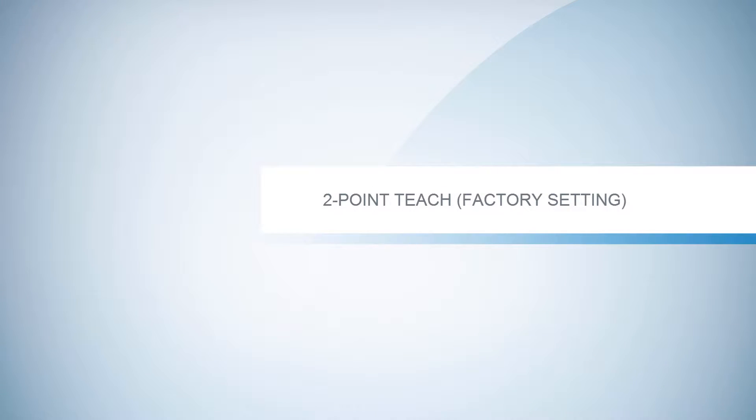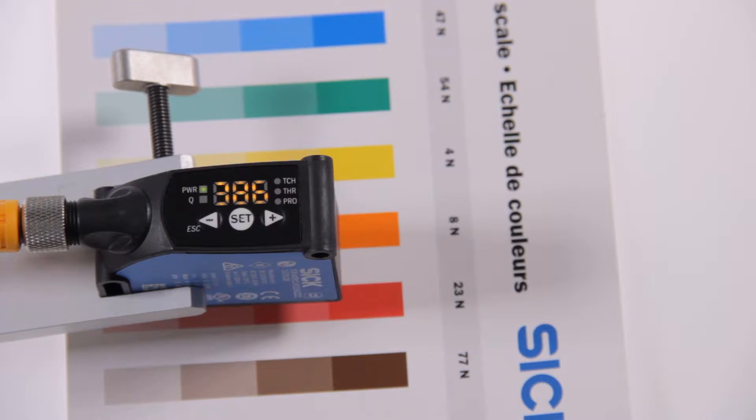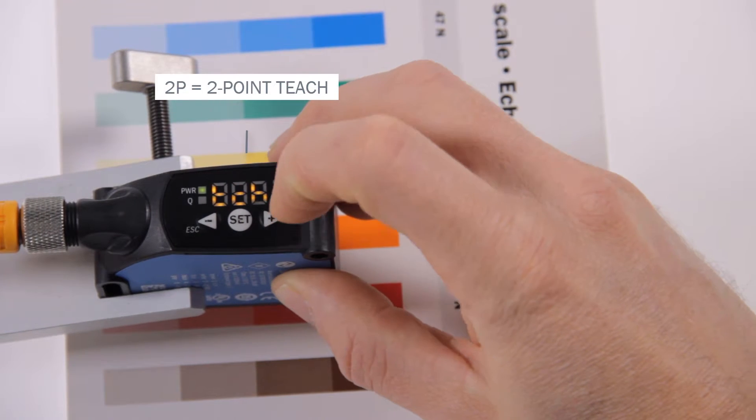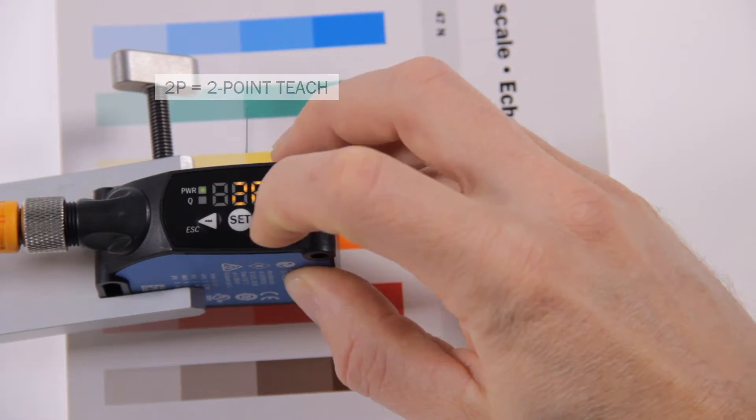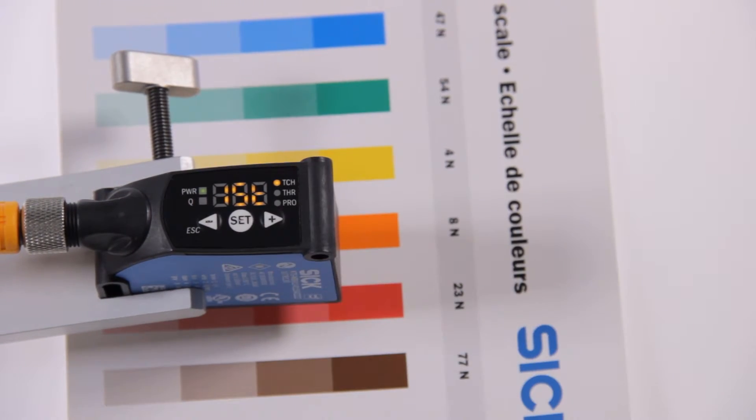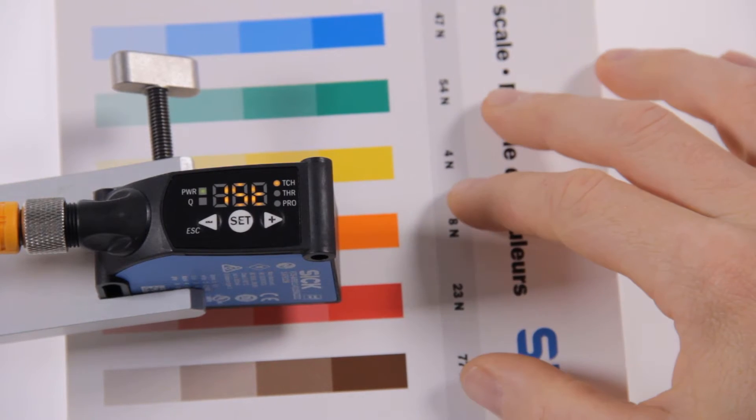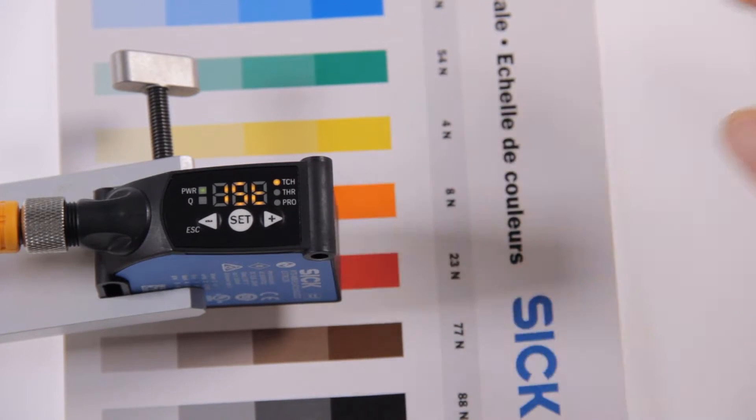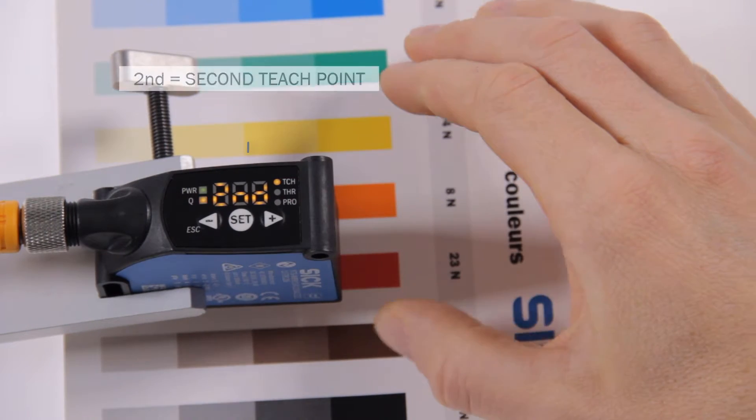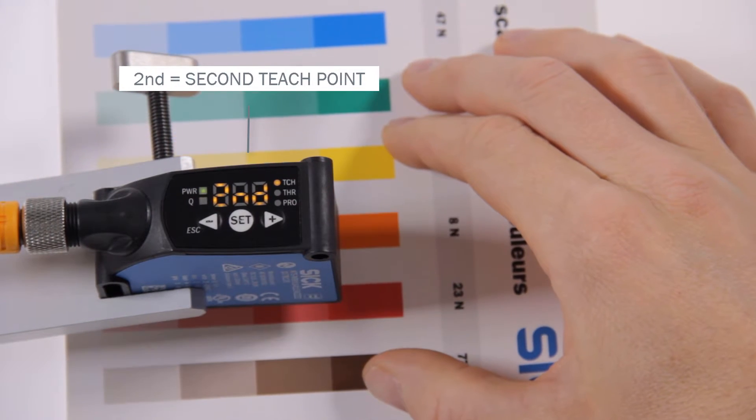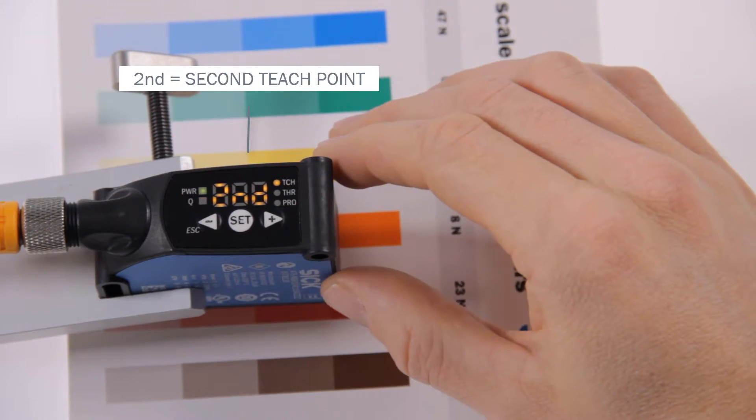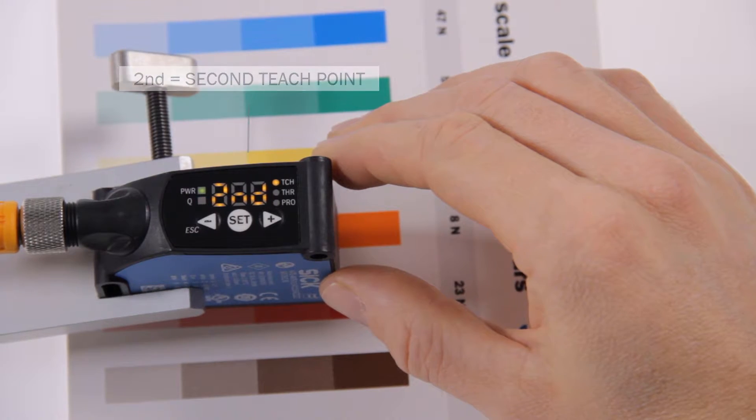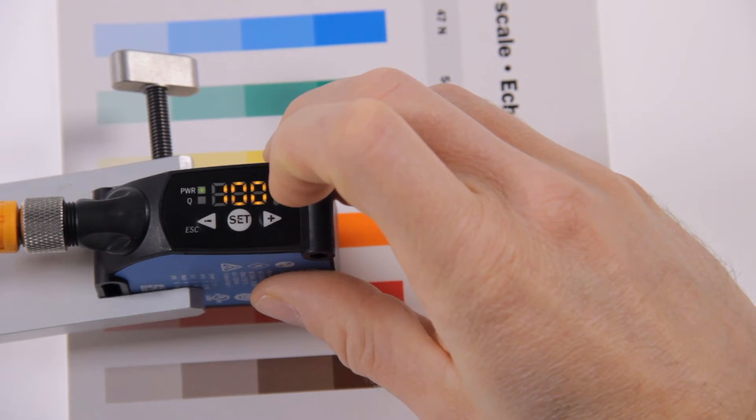2-point-teach factory setting. Select the teach-in menu 2P for the 2-point-teach-in method and confirm with SET. The display shows first, requesting the first print mark. Place the print mark under the light spot and press SET. Now second is displayed, indicating that the second teach-point is required. Now move the background under the light spot and press SET again.